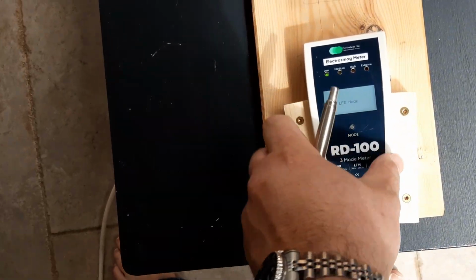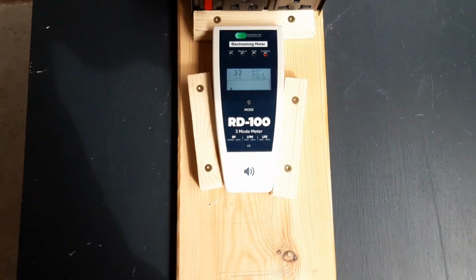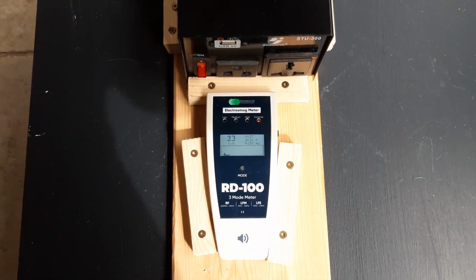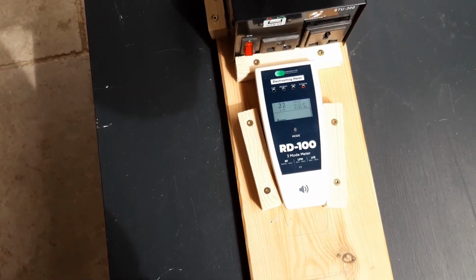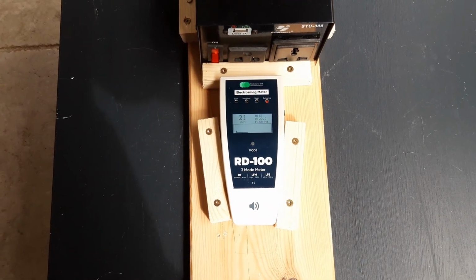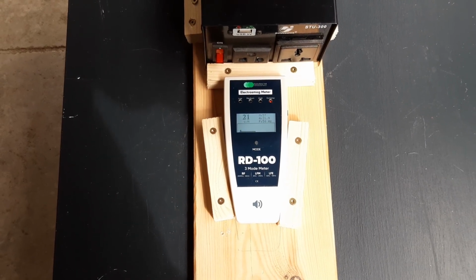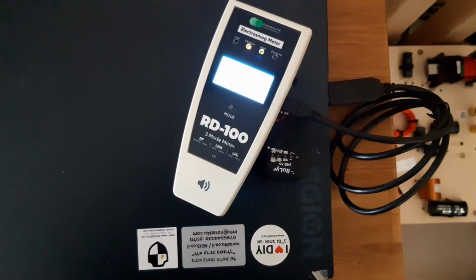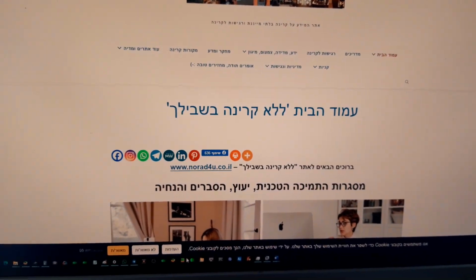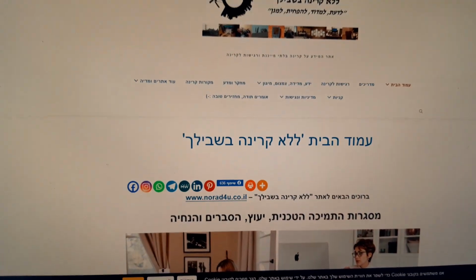I'm writing all the outcomes on a piece of paper. And now doing it also for electric field, getting 23, 22 volt per meter. So we saw differences between the reference meter and our meter, the meter that is going to go out for the customer. So I'm connecting the meter to the PC via a special cable and operating special software that the manufacturer has made for me.